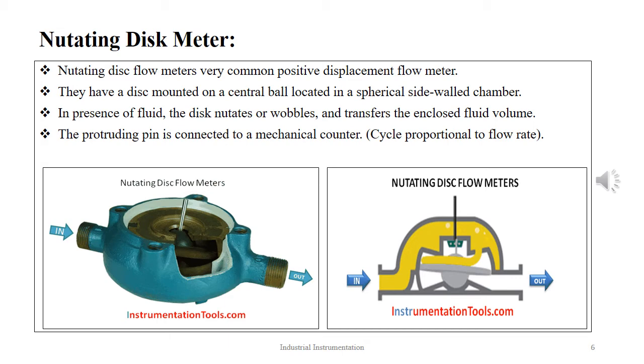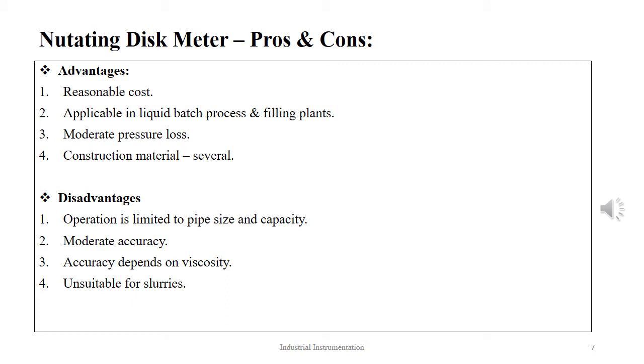As is true with all positive displacement flow meters, viscosity variations below a given threshold will affect the measuring accuracies. The advantages of the nutating disc meter are reasonable cost, applicability in liquid batch processes and filling plants, moderate pressure loss, and wide construction material range.